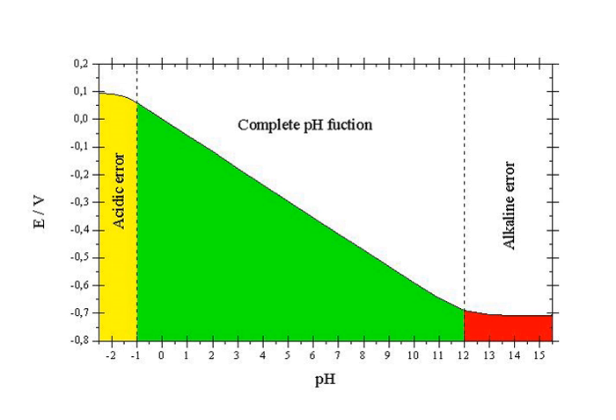All glass pH electrodes have extremely high electric resistance from 50 to 500 megaohms. Therefore, the glass electrode can be used only with a high-input impedance measuring device like a pH meter, or more generically, a high-input impedance voltmeter which is called an electrometer.